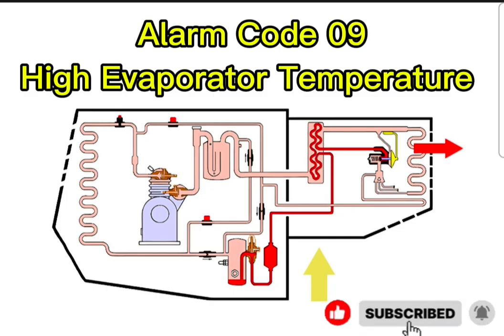Right. You go to the digital tape. The manual dictates that the absolute, always first step in the diagnostic procedure is to download the Service Watch data logger. Essential. And you do this using a piece of software called the WinTrack Service Tool. It explicitly says the technician must review this data at the technician level to see the conditions present exactly when the alarm was set and when it was cleared. Yeah. But what does that actually look like in practice? Is it just a text file that says it got hot at 2:00 p.m.?